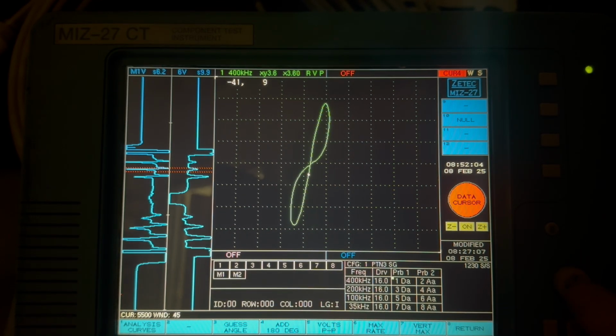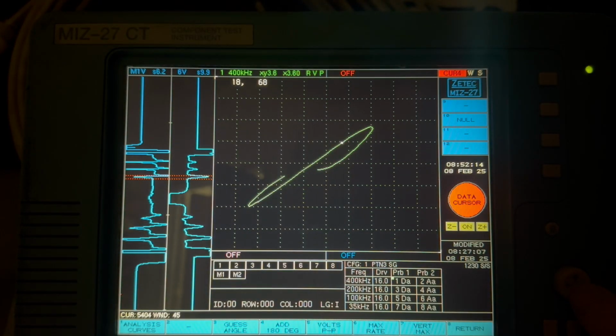Similarly, when we go a little bit further into the material to the 20s, which are placed around the circumference, we have even more phase lag. That's probably about 140 degrees-ish. So clearly we can see that there's a difference with the phase angle for the different depths. So what we can do with a phase versus depth calibration curve is tell the software that the 100% signal that sits at 40 degrees, well, it's 100%. That's what we input into our sizing curve.